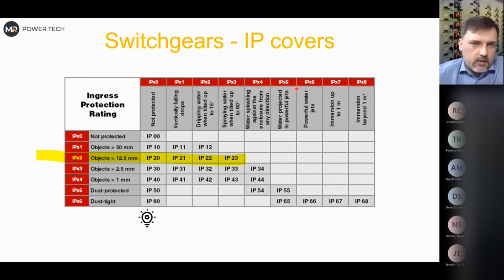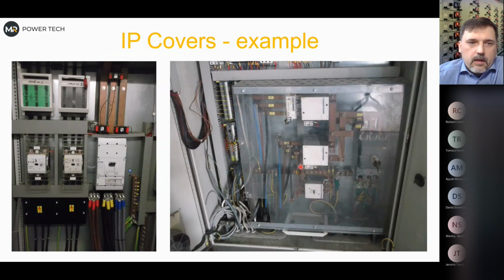IP cover, so ingress protection. This is probably the best thing you can do, and the easiest and cheapest thing you can do in your switchgears, to increase your safety, not only for arc flash but also for shock hazard. We recommend keeping IP2X or X2 level, so finger safety. There are multiple levels of IP, whatever you would like to do, from nothing to water immersion, but I will show you how it looks in real life when I go on site.